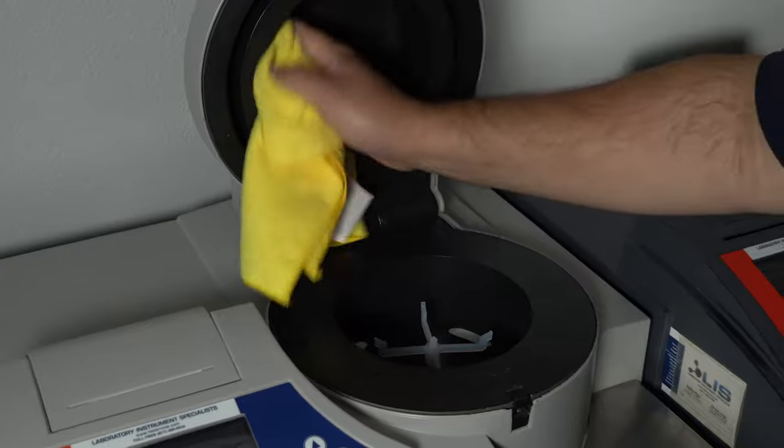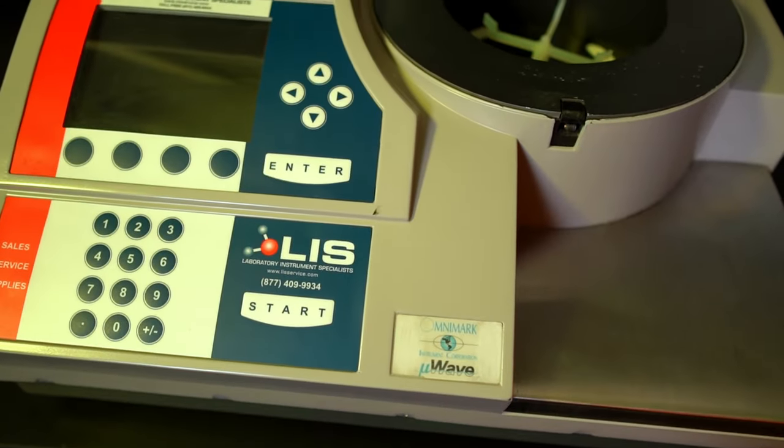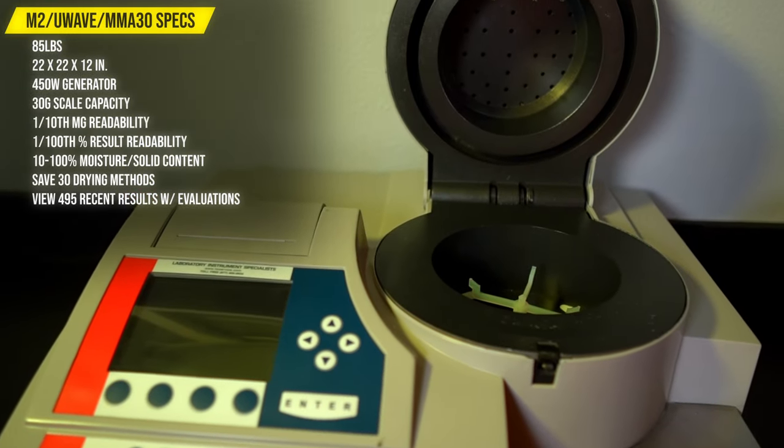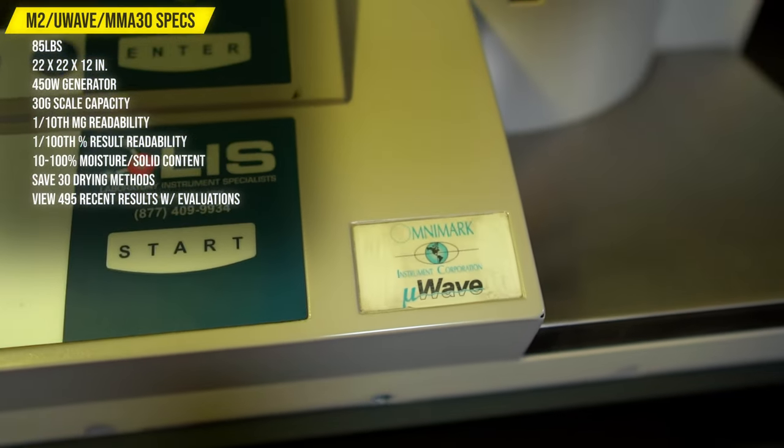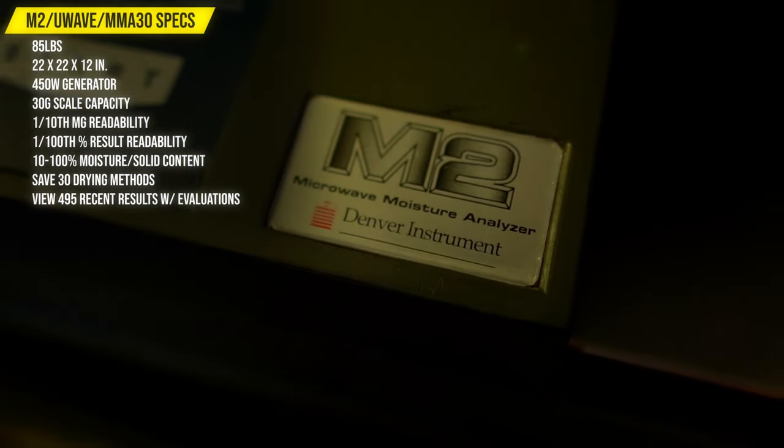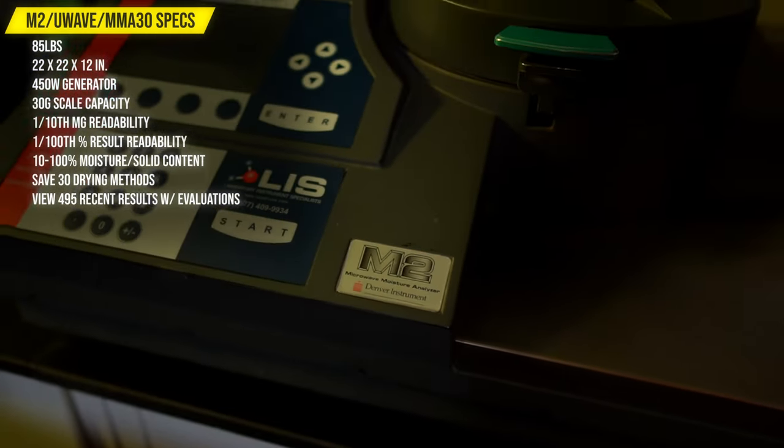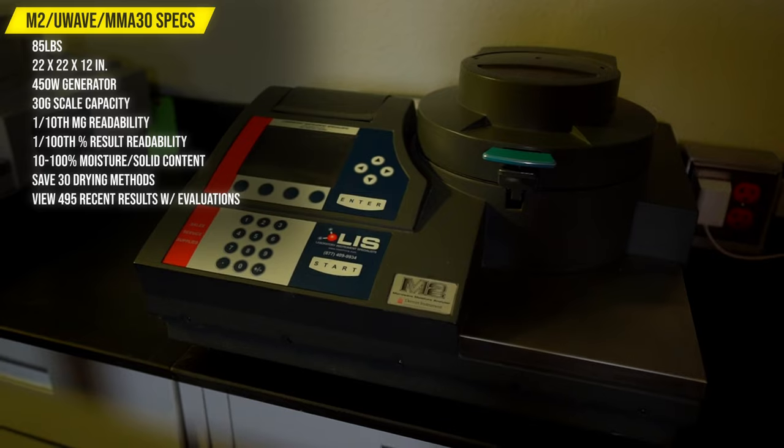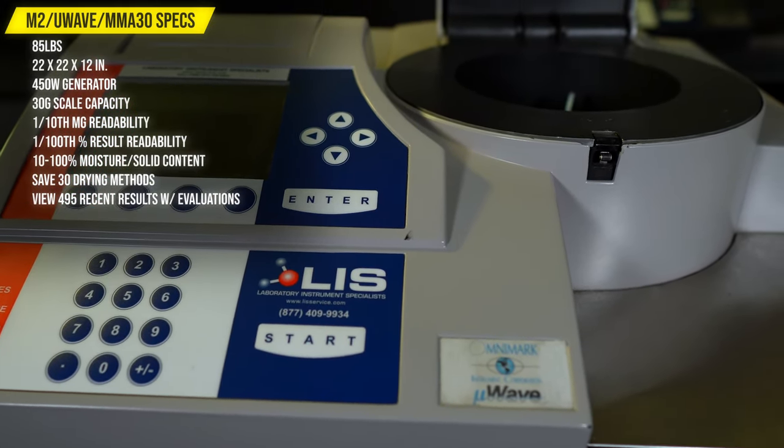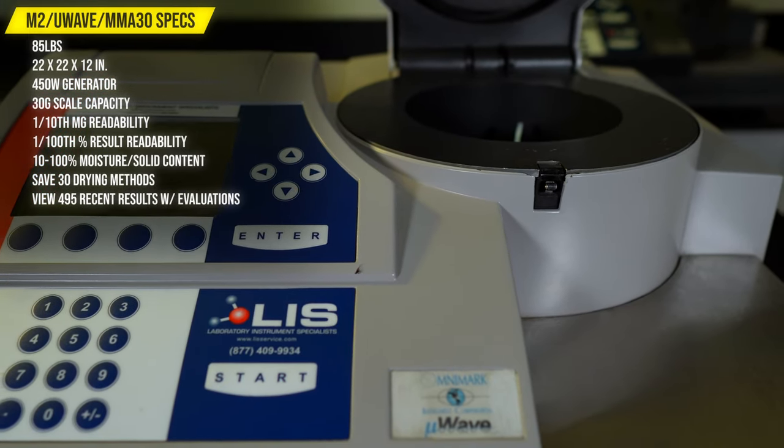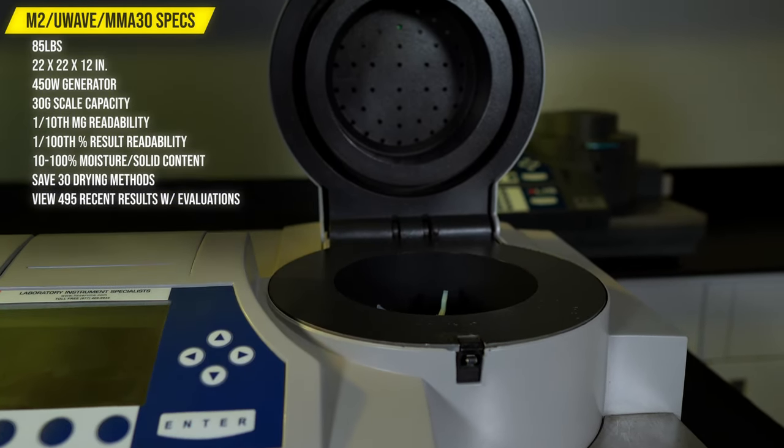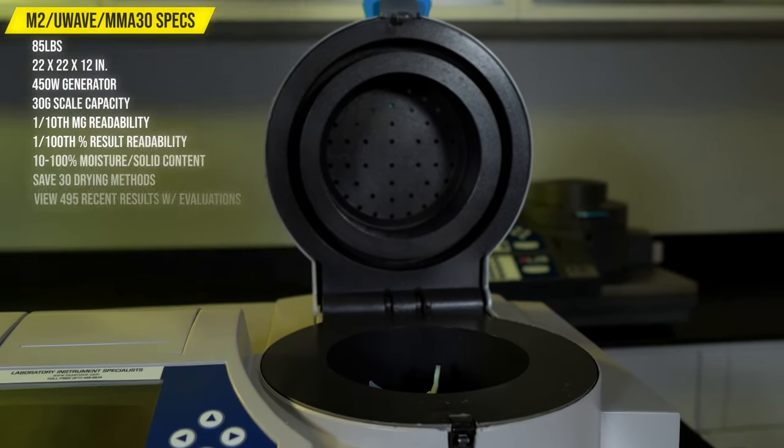Now, we'll go into a brief overview of these instruments. Both the M2 and the U-Wave have the exact same shape and size, weighing 85 pounds and measuring 22 by 22 by 12 inches. The instrument is heated by a 450-watt power generator. The maximum scale capacity is 30 grams with a readability of one-tenth of a milligram. Testing results have a readability of one-one-hundredth of a percentage while being able to determine between 10 to 100% of moisture or solid content. You can save up to 30 different drying processes and view 495 recent results with evaluations.